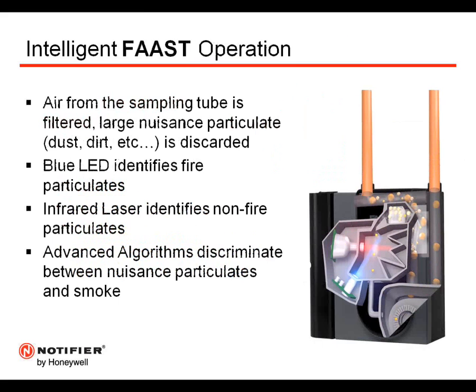The third stage in our filtration methodology is the detection method itself. FAAST uses a blue LED to detect low concentrations of smoke from a wide array of fires, and an infrared laser to identify particles not associated with combustion. Then onboard algorithms interpret the signals from both of these sensors and make the decision to either reject the nuisance particulate or activate it in the presence of smoke.